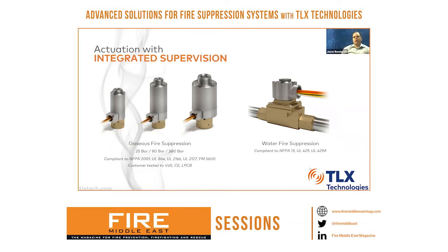And what eventually happened is that they came up with a code in which, if you follow that same NFPA code, anytime one of these devices on gaseous fire suppression systems has been removed, there needs to be an audible or visual signal at the control panel alarming that personnel that that device has been removed. And basically what this does is give the personnel some sort of indication that the system is not triggered appropriately, and that they need to make sure that these actuators are replaced back onto the system.